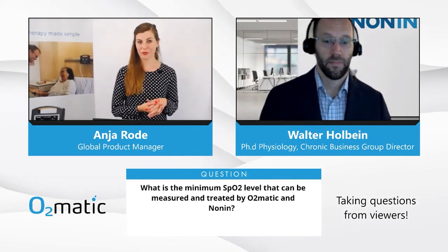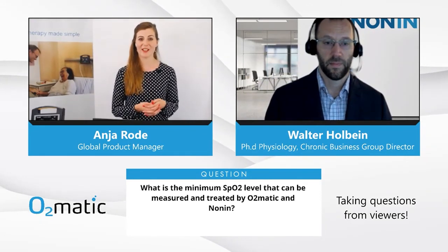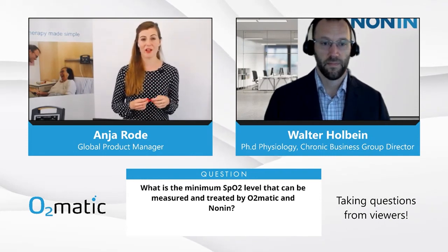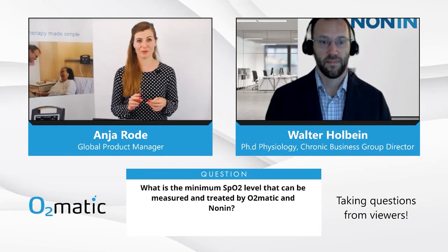Good. I think we can take one more question and then I think we should round up. What is the minimum SpO2 level that can be measured and treated by O2matic and Nonin? I read this as two different questions because I know that you can measure a lower SpO2 than we are treating. O2matic has a treatment interval for patients between SpO2 80 to 100, and if the SpO2 is below 80, then it will start alarming. But you can choose your treatment interval between 80 and 100.